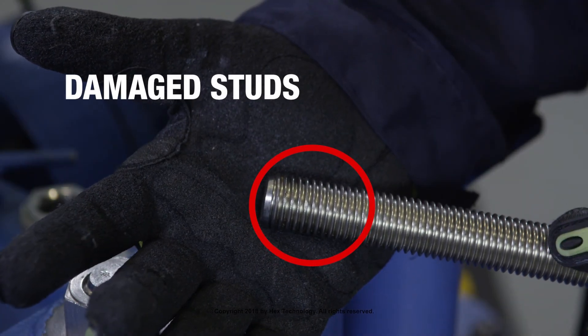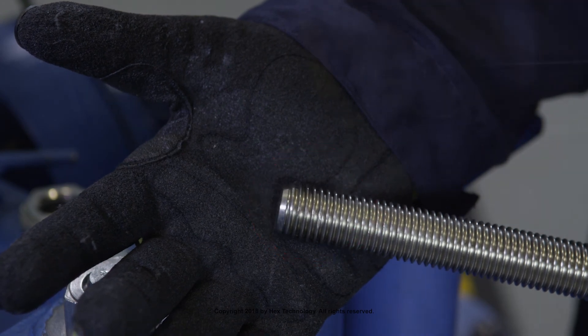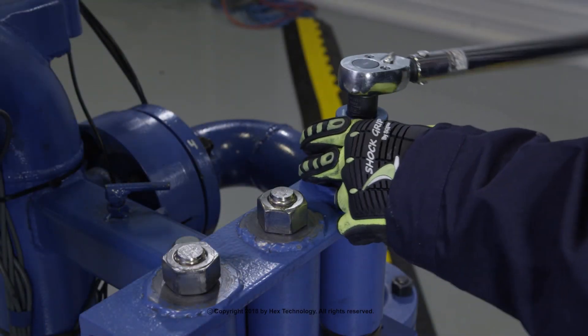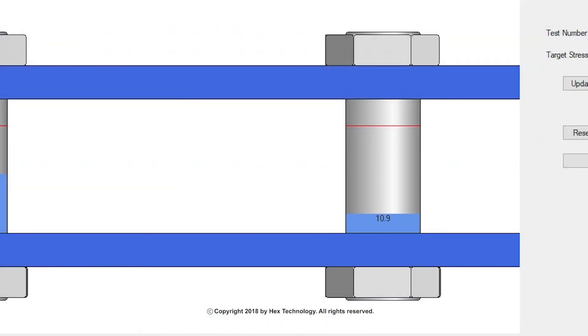This stud has minor thread damage. While this may be difficult to see, it can greatly affect bolt load or stress values. This test shows well under the specified target bolt stress as a result.